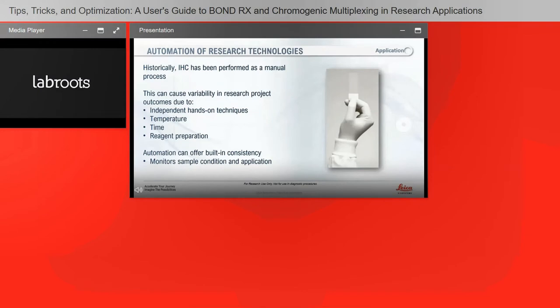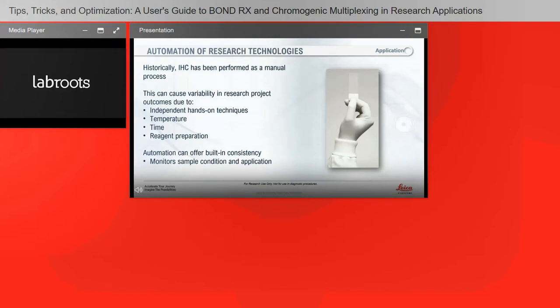Historically IHC has been performed as a manual process, which can cause a lot of variability in research project outcomes. There are various points to control: independent hands-on techniques lead to user-to-user variability; temperature variability requires that your microwave and pressure cooker are at correct temperatures; time variability means researchers are running around with timers on their lab coats. It is a very time-sensitive assay. Also, DAB is highly carcinogenic, so mixing DAB is not the safest procedure. Automation can offer built-in consistency and can monitor sample condition and application.